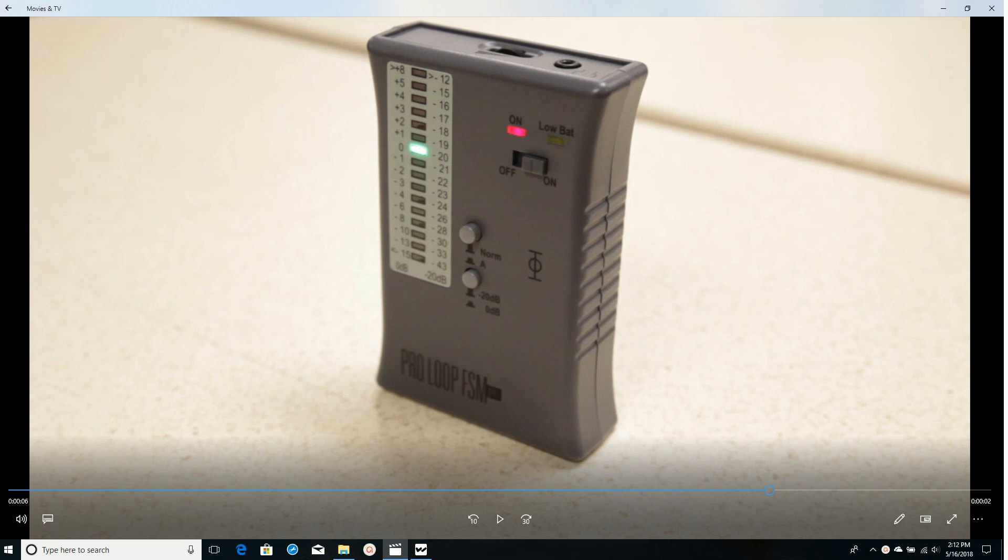This should be measured at 5 feet above the floor throughout the entire looped area. Remember we're using a 1 kHz sine wave and the field strength should be within plus or minus 3 dB across the entire looped area.